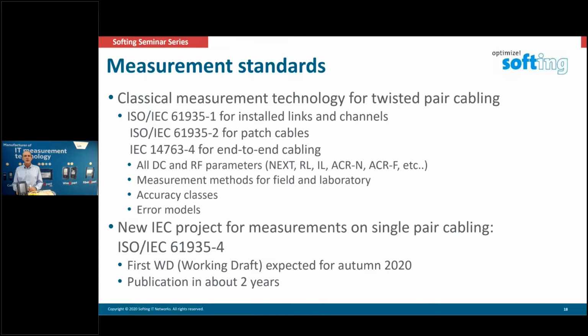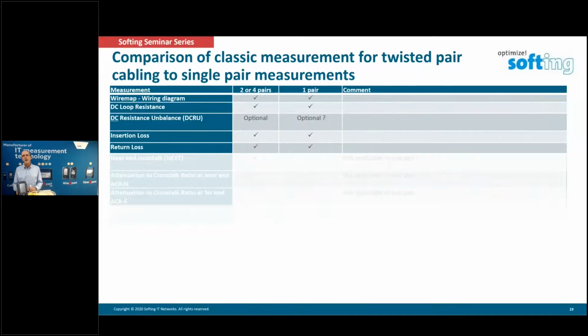If you compare 2 and 4 pair measurements with a 1 pair measurement, there are things that are very similar. For example, wire map - you need to do a wire map, less wires, yes, but you need to at least prove that the 1 pair and optional shield is there. DC loop resistance measurement is an important measurement - we do that on 2 pairs, and on 1 pair as well.